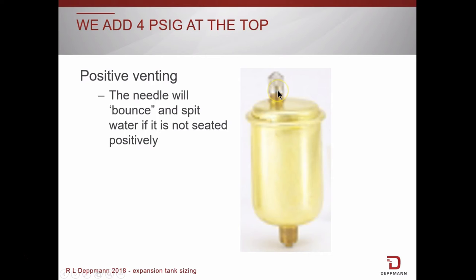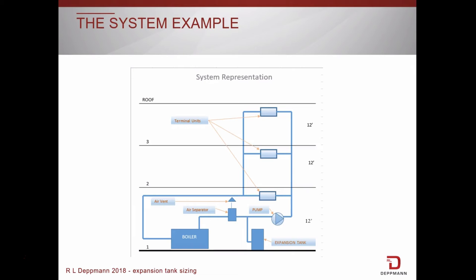If we don't, the pin in the automatic vents shown here will bob up and down with pressure changes and the vent will spit water out. The second reason is to make sure that there is enough pressure to keep the water from flashing into steam if the temperature somehow gets above 212 degrees. 4 pounds is enough pressure for about 215 degrees heating hot water.